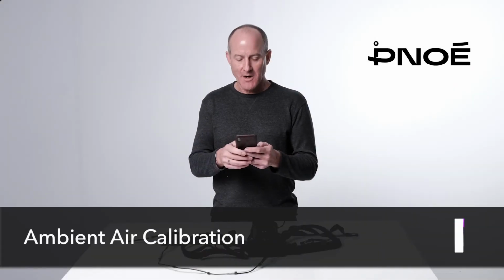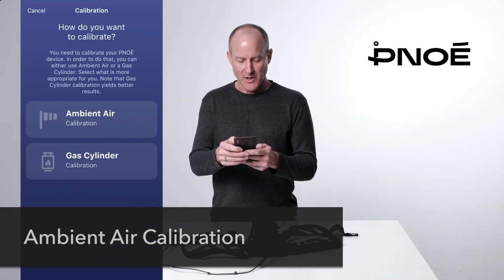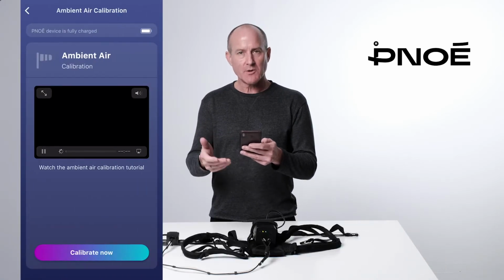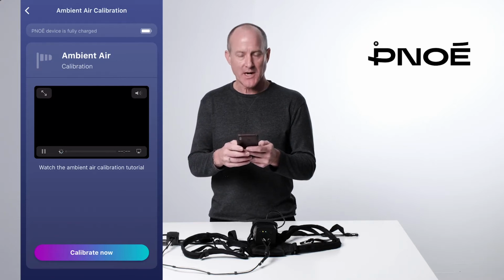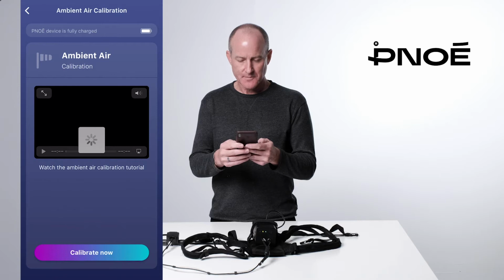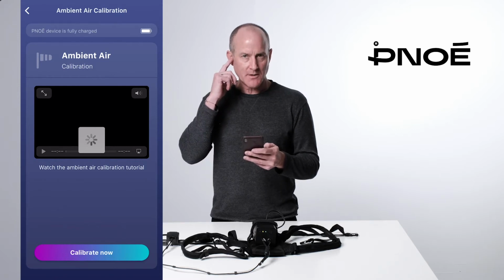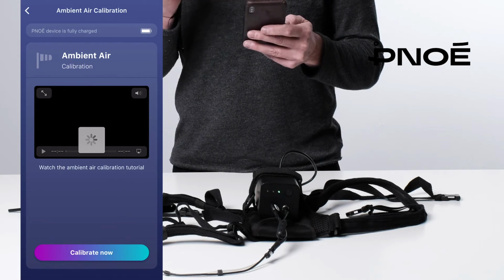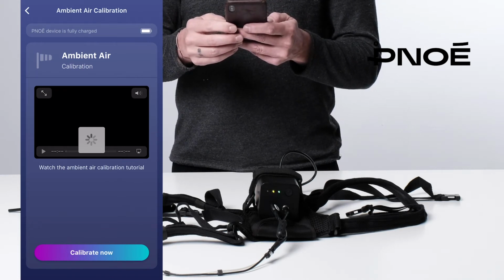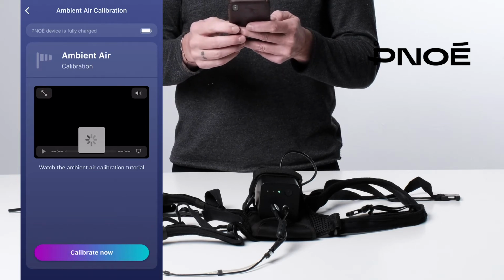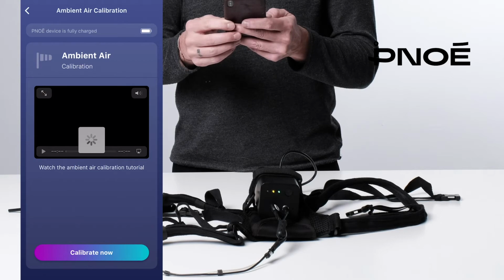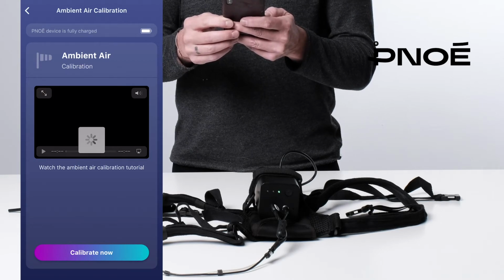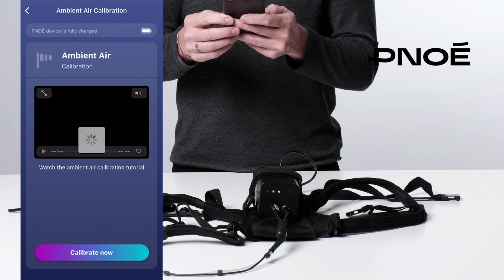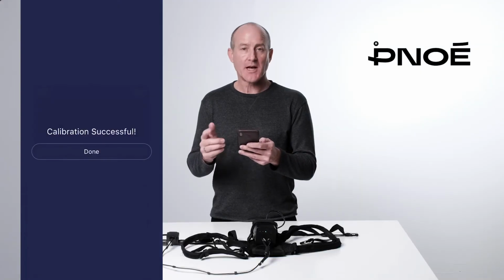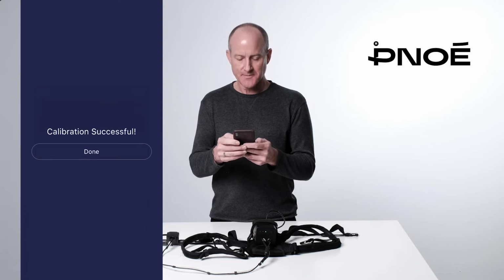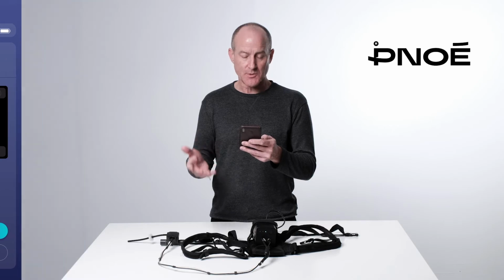Now we'll complete an ambient air calibration. Select ambient air calibration. You'll see a video is available to help you. Hit calibrate now. You'll hear the pump turn on, and you'll also see the light flashing quicker. It'll take a few seconds for the calibration to be completed. And you'll see calibration successful and done. Select done. And then you're able to start the test.